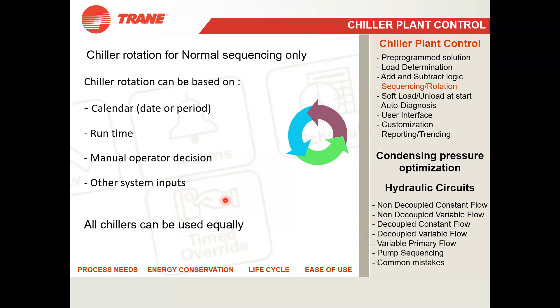So what is the aim actually? So that all chillers can be used equally. I told you that one chiller is giving maximum efficiency when it is running on full load. So it should not be like that, where all 3 chillers are running and all are at 30% load. That will be a wastage of power. So the ultimate motto is that all chillers can be used equally, and whatever the customer wants from here, all this can be programmed in the CPC.